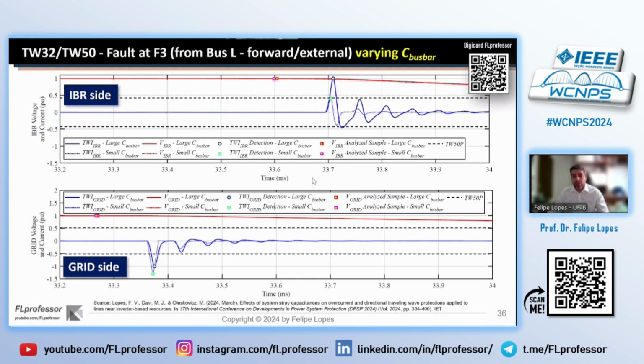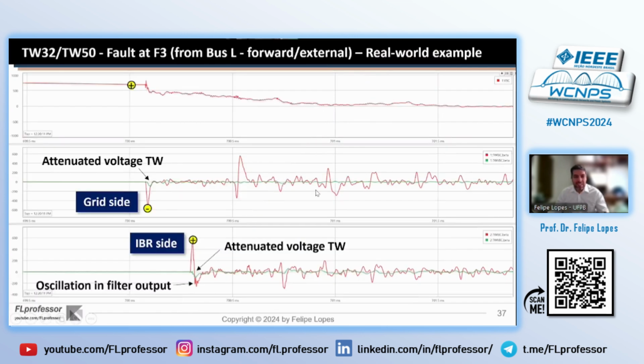And just to make sure that you will believe in me, this is a real case where we can see the wavefront on the IBR side, the oscillation that I mentioned earlier to you. So this is real. The stray capacitance effect is real, but we can see that the wavefronts can be properly detected in the real system. So it shows that travel wave protection functions are indeed promising.